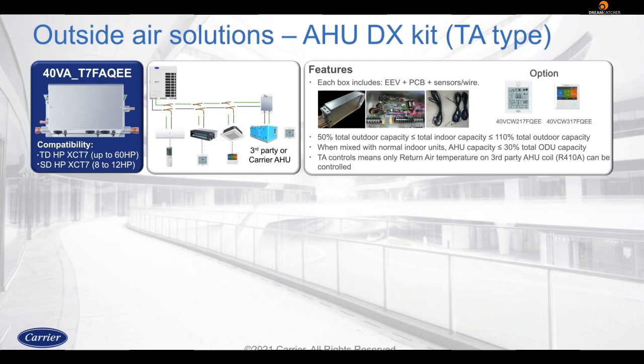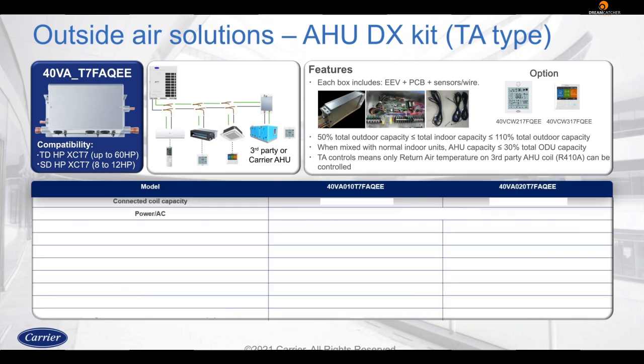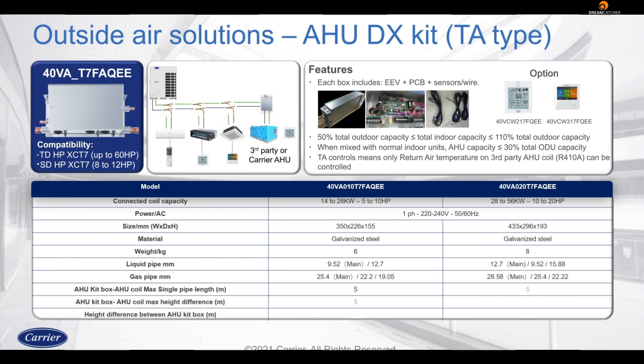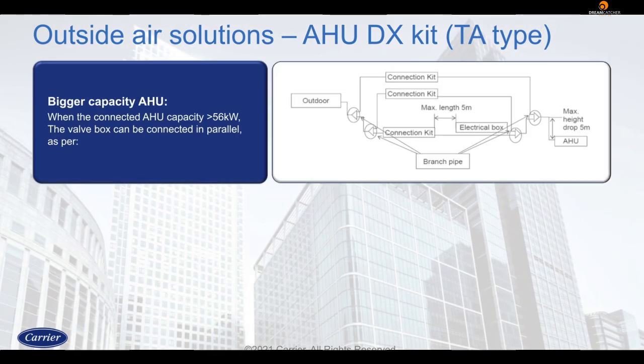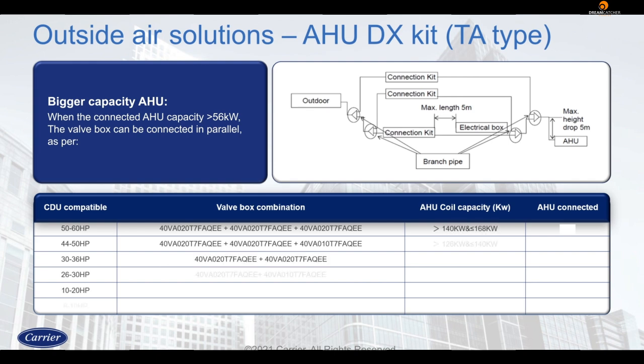With the DX kit, our XCT7 outdoor unit can connect with AHUs and other indoor units. The combination ratio for connection mix with VRF indoor units is 50% to 110%, and AHU capacity shall not exceed 30% of total system capacity. You can also have 1-to-1 connection. The combination ratio for AHU to VRF alone will be 90% to 110%. If the solution you design is connected to a bigger AHU of capacity more than 56 kilowatts, then the kit can be connected in parallel, as shown here.